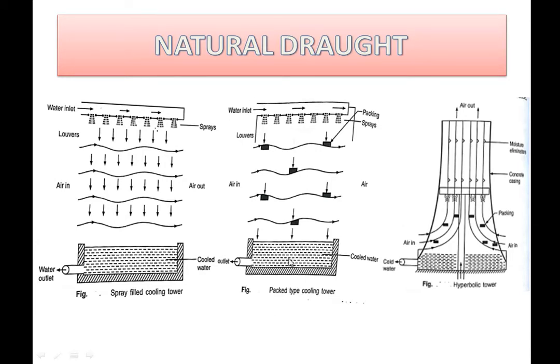The third is the hyperbolic tower. As you can see, the shape of the hyperbolic tower is that of a chimney. It creates a natural draught which makes it more efficient. From here the water is sprayed and from the bottom the air inlet is present. The air inlet goes through the packing and then to the outside air due to the natural draught, and the cold water is collected at the bottom of the hyperbolic tower.